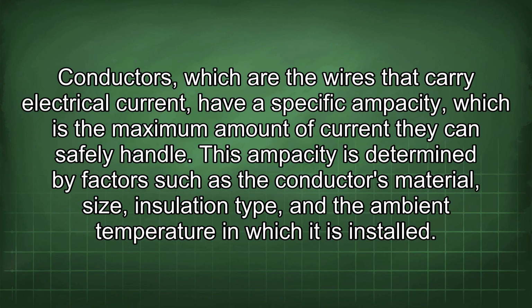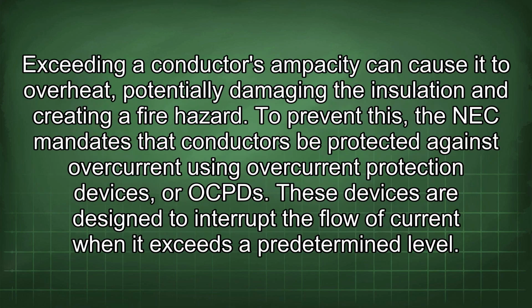This ampacity is determined by factors such as the conductor's material, size, insulation type, and the ambient temperature in which it is installed. Exceeding a conductor's ampacity can cause it to overheat, potentially damaging the insulation and creating a fire hazard. To prevent this, the NEC mandates that conductors be protected against overcurrent using overcurrent protection devices, or OCPDs. These devices are designed to interrupt the flow of current when it exceeds a predetermined level.